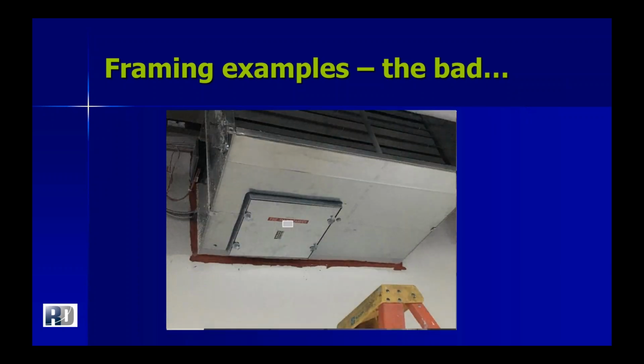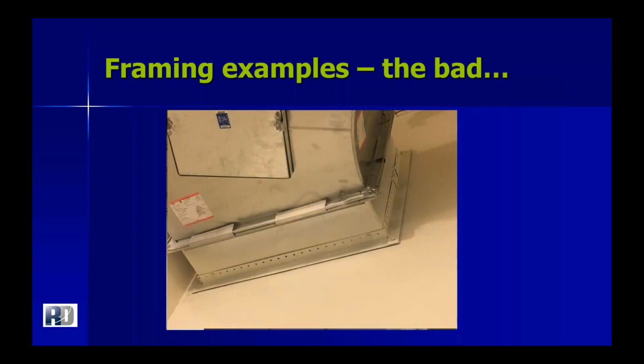On this, you can see that the fire smoke damper is fire caulked into the wall, and that is a no-no. You do not fire caulk fire dampers or fire smoke dampers. You can fire caulk a smoke damper, but in regards to fire smoke dampers and fire dampers, you need a retaining angle, and then you can, should you choose, caulk the retaining angle. And here we have one of those retaining angles, and you can see that the screws are missing. So these retaining angles have not been screwed into the sleeve or the wall where they're supposed to be.